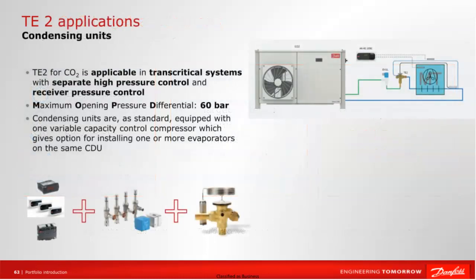For applications such as condensing units, thermostatic expansion valves can be used in a transcritical system with a high pressure valve and a gas bypass valve. The maximum differential pressure that can be used is 60 bar. Condensing units designed to work with CO2 are as standard equipped with a variable capacity compressor, which allows one or more evaporators to be connected to the same unit. In such a configuration, it is important to install a solenoid valve in the liquid line, in addition to the thermostatic expansion valve. Then the previously mentioned Optyma controller can be successfully used.